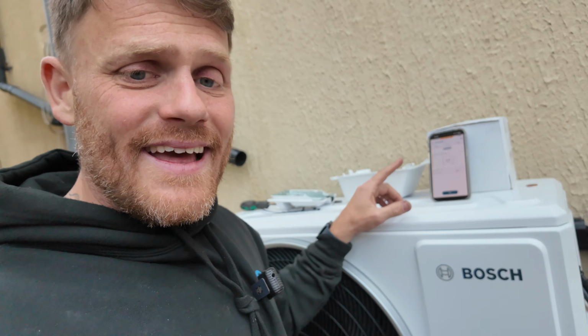So the number we're looking for here, there's nothing to say what you can go down to, you just want it as low as you can, right? We'll show you why in a minute. So we're just going to let that run, get that number down as low as possible, to make sure we've got a really good vacuum on that system before we open anything up.